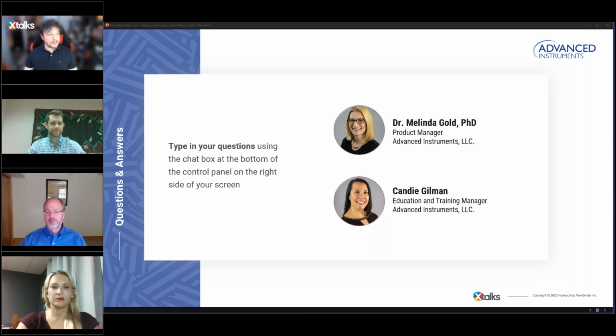All right, very good. That's very helpful. Thank you. The next question is wondering how often I should test pipettes between calibrations. Oh, another good question. Let me take that one. In the overview of the standards, Candy mentioned our recommended calibration and test frequencies, but that's a good starting point. Some guidelines and standards give minimum requirements, minimum time spans and frequencies for calibrations and routine tests. But it's important to understand that the calibration frequency and test frequency really depends on your own laboratory's risk assessment. And that really should be the foundation of developing the frequency for calibrations and routine tests.